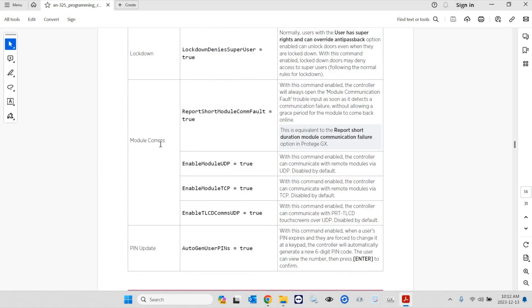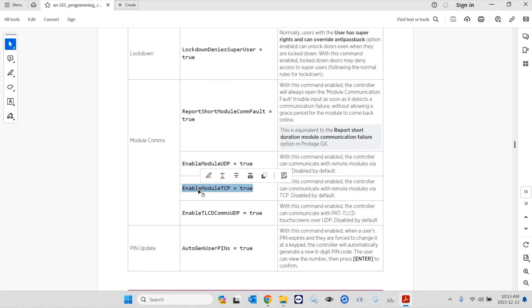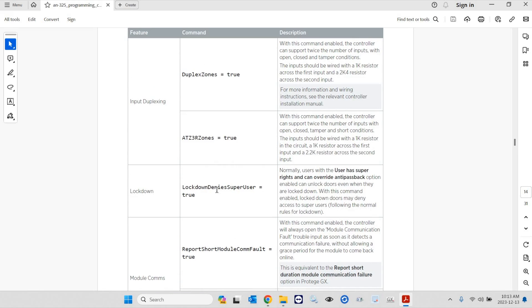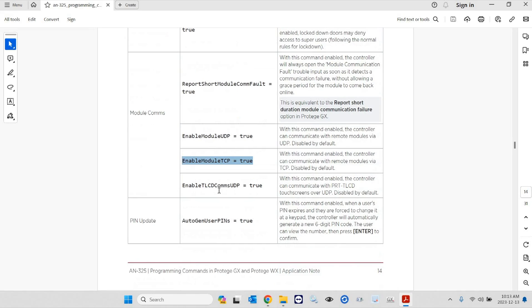As an example, when you have some modules on the Ethernet network — for instance, this is the command to use for the PRT-MNR2, and this will open the port for the entry stations. There's also a command to enable ping and similar functions. If you have an MNR2 on a site and for some reason you're not seeing the modules behind the MNR2, you will need to enable the UDP port on the controller. You just set this command, which by the true variable is going to enable the port. So most probably if you aren't able to connect the MNR2, that's the reason why.